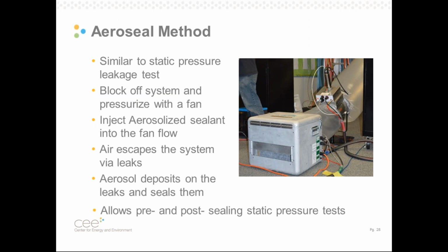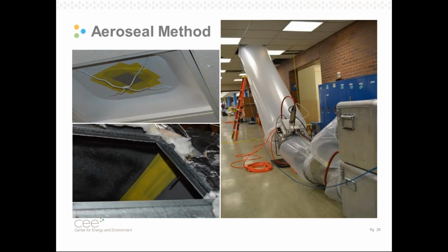There are two extremely important aspects to this Aeroseal process. First, it requires very minimal duct access. You essentially just need an access panel or somewhere you can inject this fan flow with sealant. And secondly, it has a calibrated fan in its fan box. This means that before, during, and after the sealing, you can include static pressure tests. This is extremely important because the system can essentially measure how well it did. So what does this look like in practice?